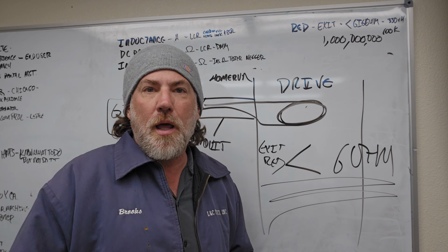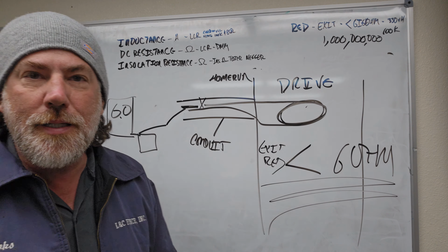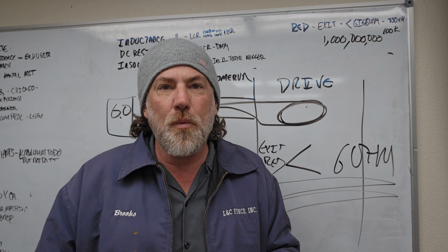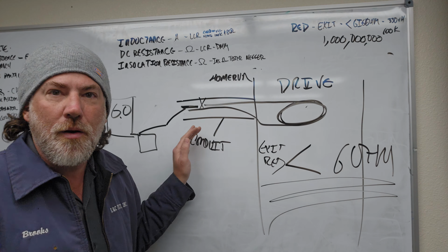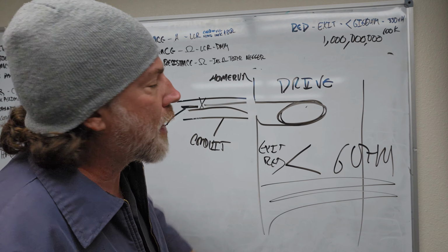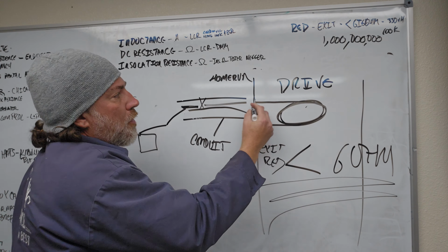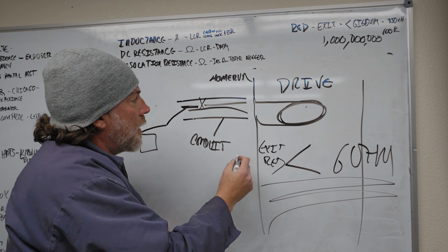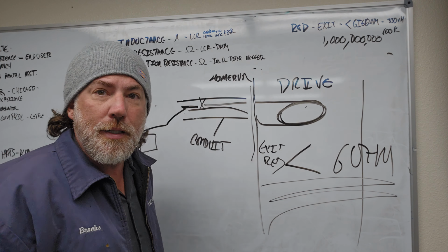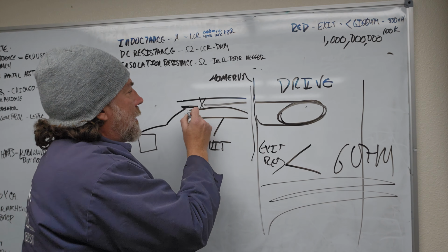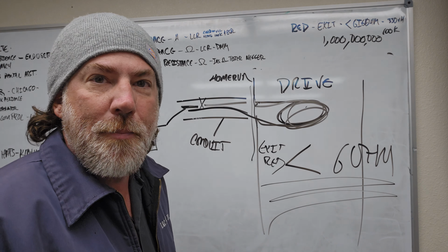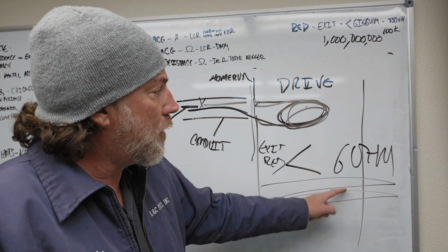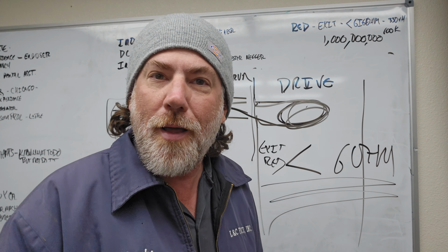No, it's actually not. So why would we test DC resistance? Why would we want to know a circuit has continuity? For this exact reason right here. Now, where does this actually happen in practical terms? You run your loop through the curb, right? Somebody comes along with the weed eater, hits that. You go to test this conductor and it's cut right there. Guess what happens? It's quite possible you could read 1 gigohm and still have a bad loop.